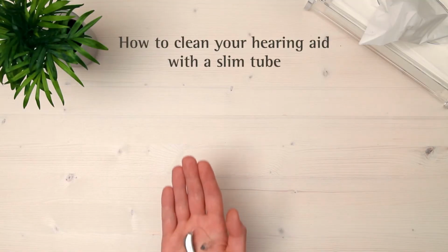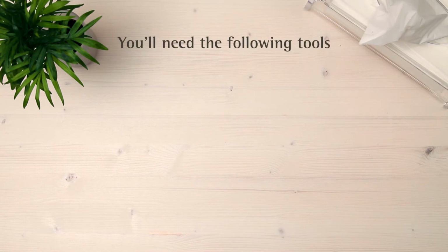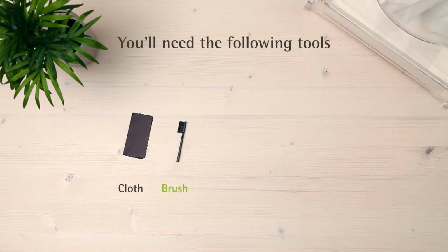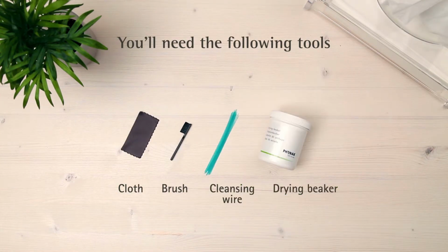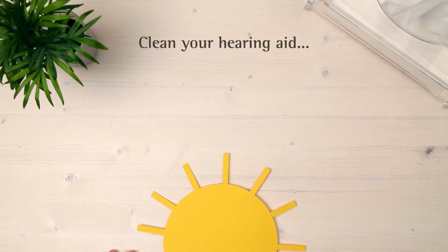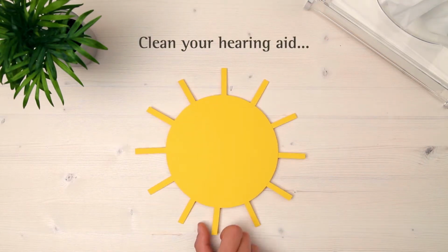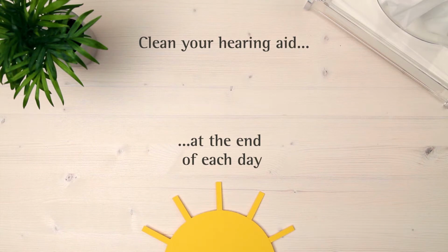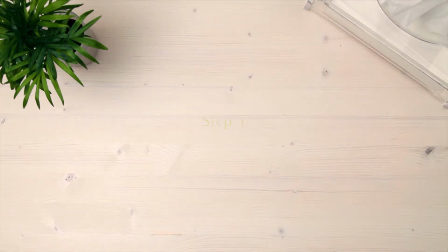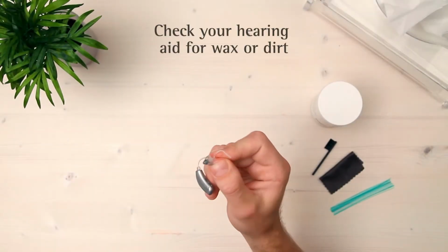This is Bolero, a behind-the-ear hearing aid with a slim tube. To clean it, you will need the following tools: cloth, brush, cleaning wire, and drying beaker. Routine care of your hearing aid is important for maintaining the best sound possible and for extending the life of your hearing aid. First, examine the hearing aid.